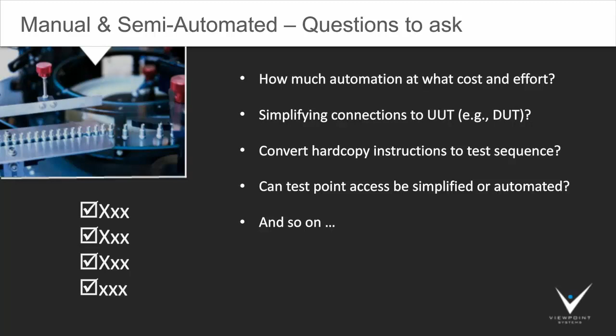So, things to consider that Viewpoint goes through when we have a customer who wants to update their test system for a manual or semi-automated test system. We look at the level of automation available in the instruments used to take the measurements. We look at the amount of time the operator spends on each step of the test procedure. And we look at ways to automate the connections between the test points and the measurement instrumentation. And based on these findings, we'll work with the customer to estimate the costs of the time to execute the steps, programming the measurement equipment to achieve more automation, and possibly replacing that equipment with more modern versions, and evaluating various connection options to make connections to the UUT as quick as possible so that you can minimize the load and unload time of the part.